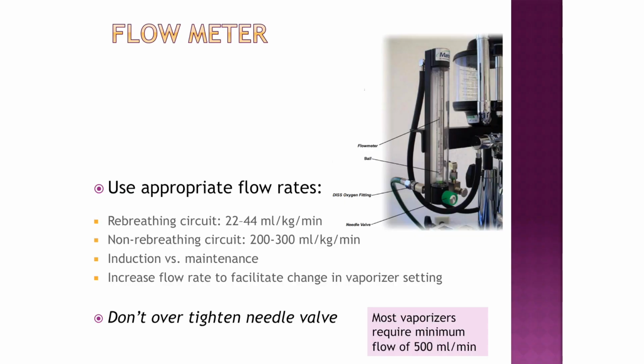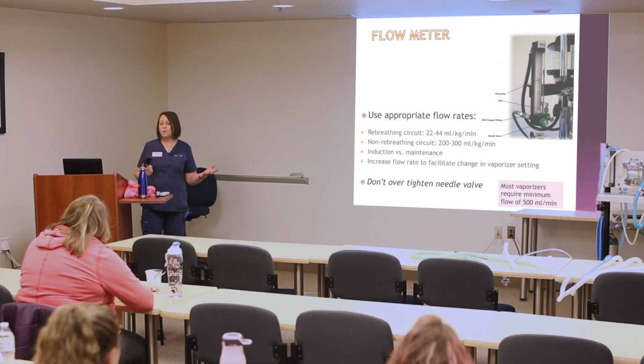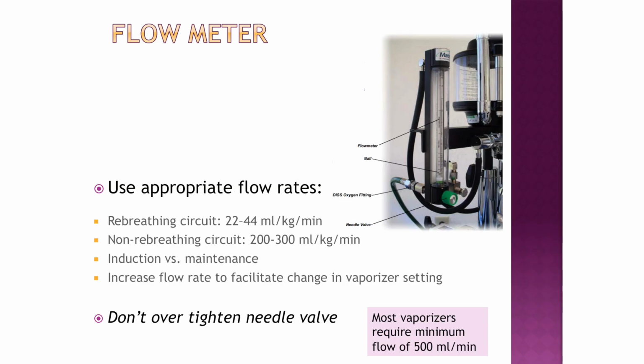This makes sense to me, but you see how much higher the non-rebreather circuit flow rates are? 200 to 300 mLs per kilo per minute, because again, we're not scrubbing out carbon dioxide. We're using high gas flows to push the exhaled carbon dioxide and waste gases into the scavenger. That's the big difference.